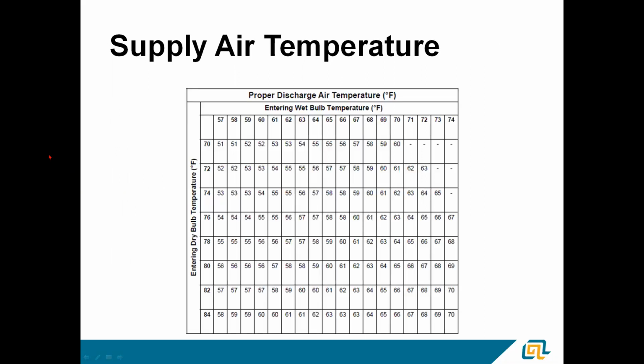I have a chart like this that's available, and if anybody would like, contact me and I would certainly be happy to send you one. This is proper discharge temperature based on dry bulb and wet bulb. You see down the left edge, you've got your dry bulb temperatures, and across the top, we've got our wet bulb temperatures. Of course, you have to have a way of measuring wet bulb. A lot of us do. I do recommend having a psychrometer with you so you can be fairly accurate. What I like to point out is as that wet bulb temperature goes up, your TD across your indoor coil starts going down. It's not as great because you're doing so much latent work, trying to pull that humidity out of the air, trying to get that wet bulb temperature down before we can start bringing the sensible temperature down as well. So this chart can illustrate, do we have the proper amount of airflow?